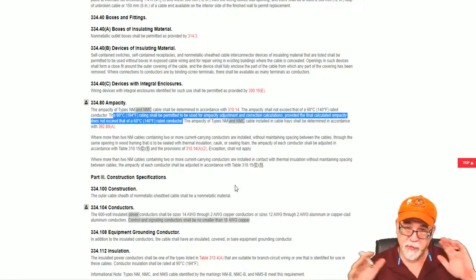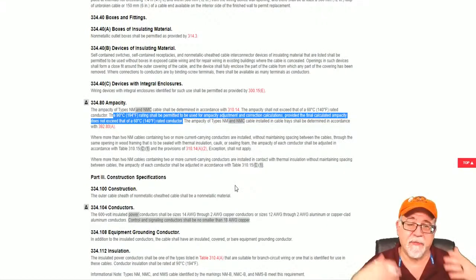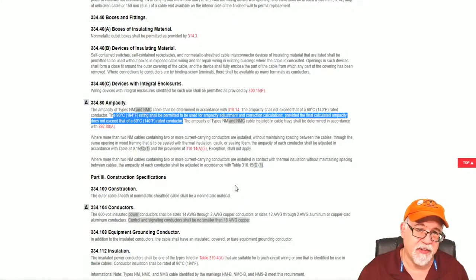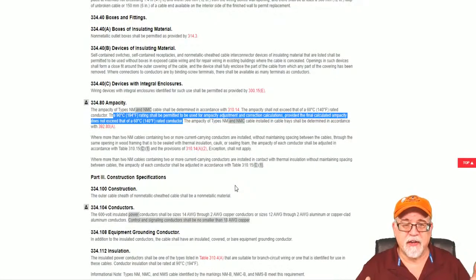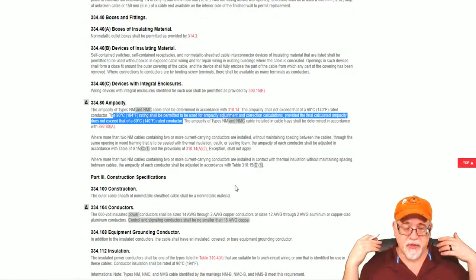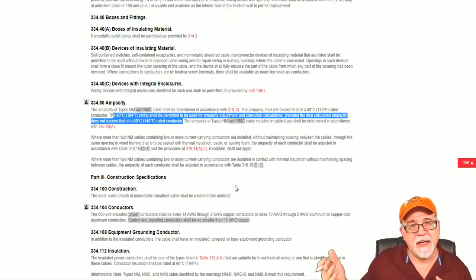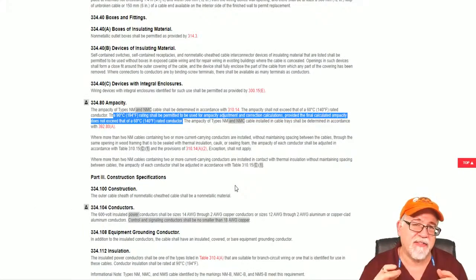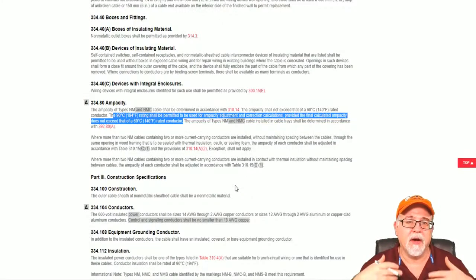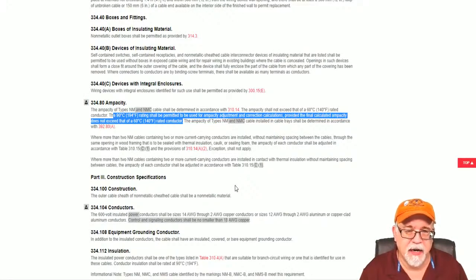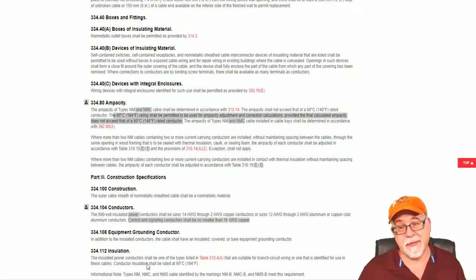Okay? You with me? All right, so that just kind of gives you the rule that says I can use a 90 for adjustment and corrections as long as I don't exceed the value that's given to me in the 60. So I tell people all the time, use the 60 degree, go choose your conductor based on the 60 degree. The only time I'm going to use the 90 is to apply adjustment and corrections to make sure that I still have a conductor that is capable of handling the load. But we're looking for a question, what is the ampacity of a conductor, okay, in this environment? Okay, so there's going to be an adjustment and correction that takes place. But I just want you to be aware of that because all this question is asking you is what is the new ampacity of a conductor, okay, after adjustment and corrections, obviously the ambient temperature. All right, just kind of wanted to clear that up real quick before we go.